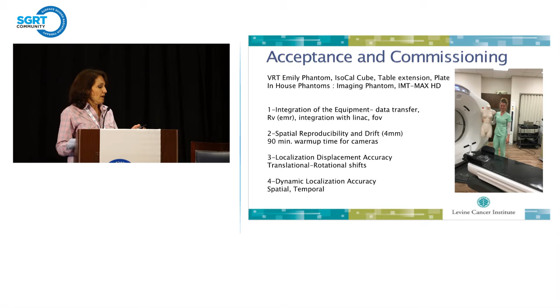And dynamic localization accuracy, spatial and temporal. In Align RT, you can set your timing, how long it goes off. You have to check that in terms of, is it 1 second? Is 1 second, actually, would it stop the beam?